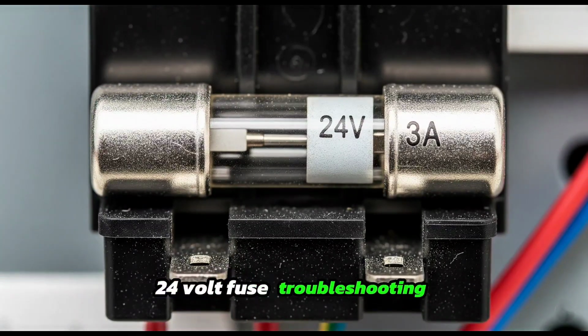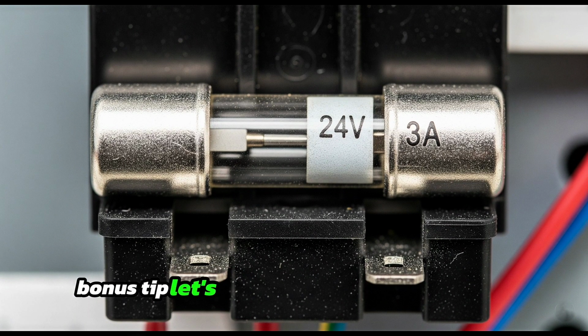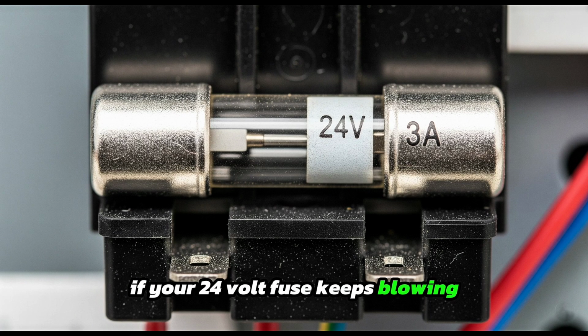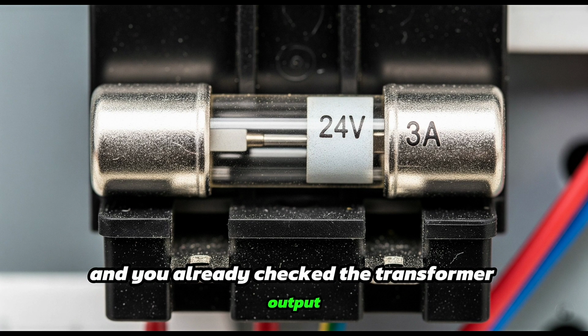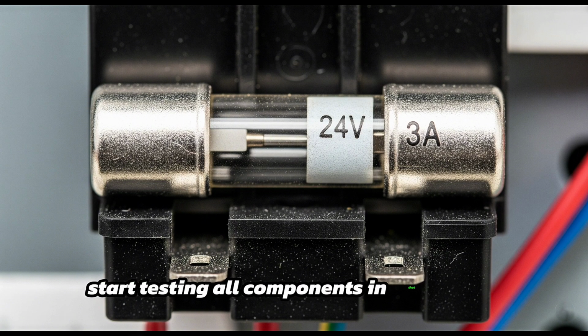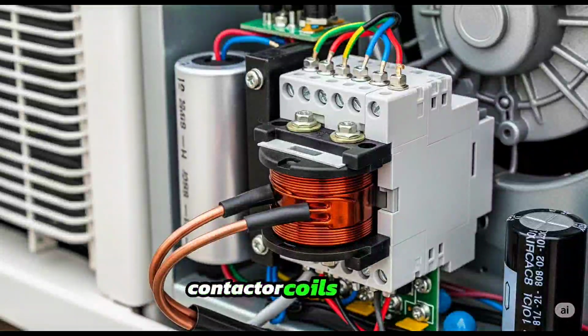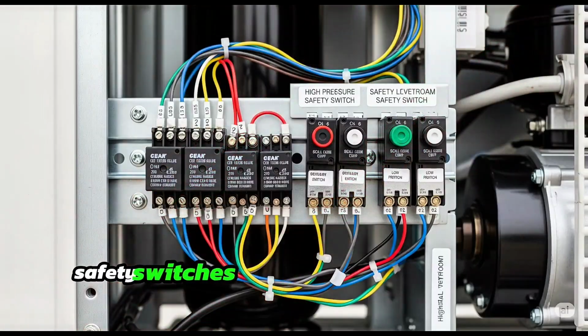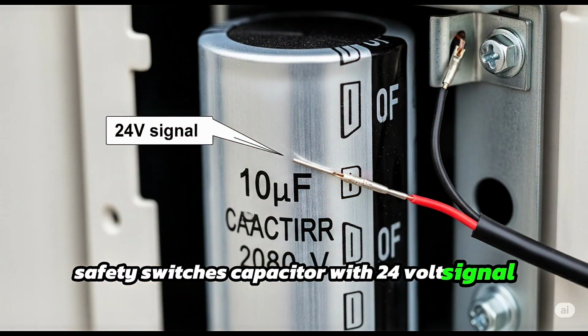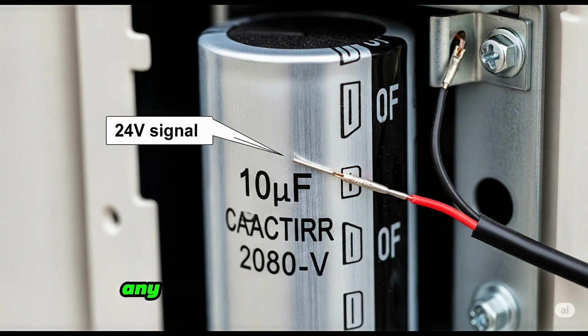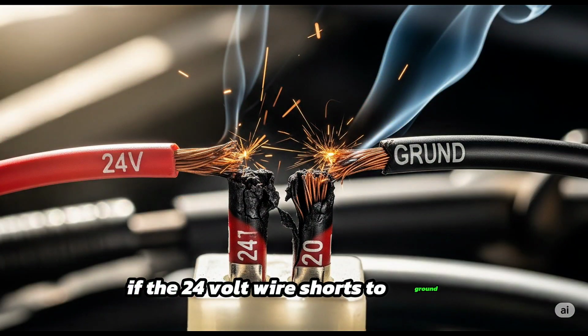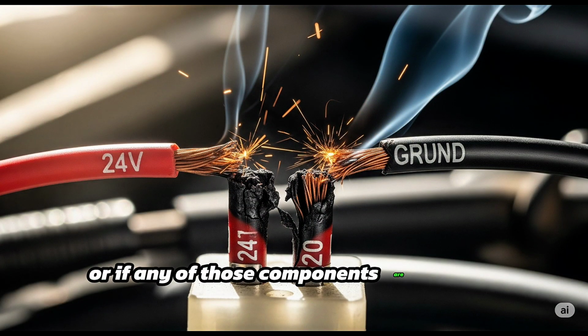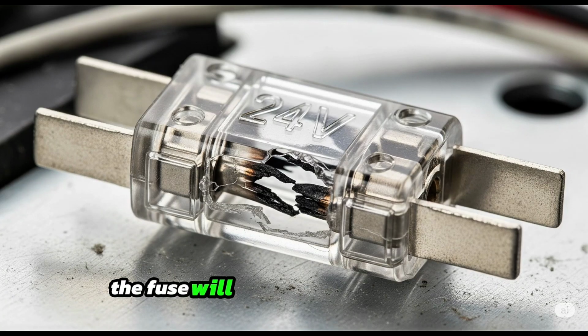24-volt fuse troubleshooting. Bonus tip. Let's go to low voltage for a minute. If your 24-volt fuse keeps blowing and you already checked the transformer output, start testing all components in that circuit: contactor coils, relays, safety switches, capacitor with 24-volt signal wire passing nearby, any part of the wire touching metal. If the 24-volt wire shorts to ground, or if any of those components are shorted internally, the fuse will burn.